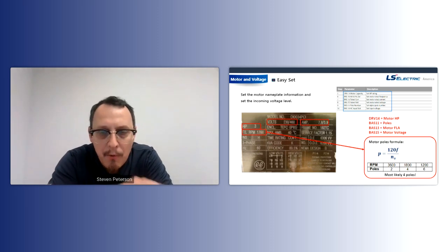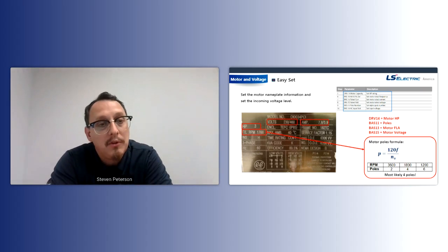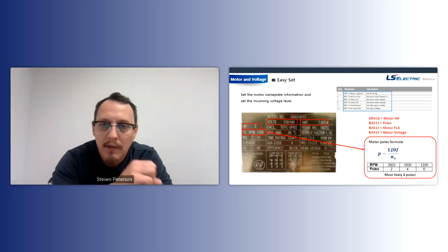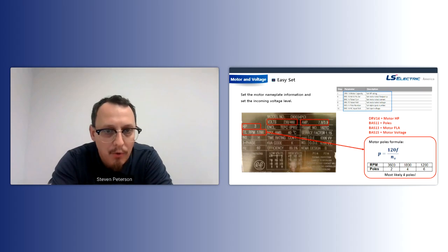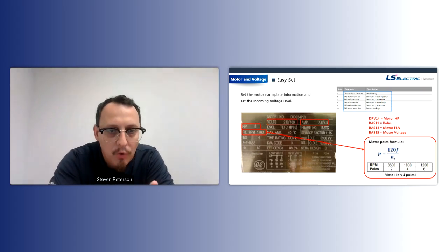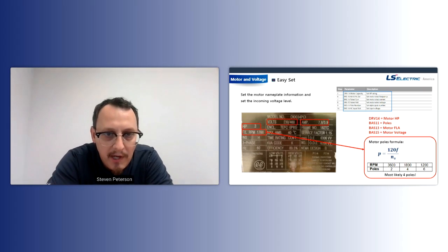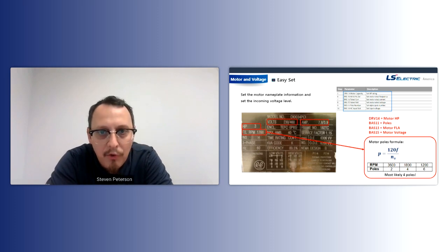The next thing is going to be your motor frequency, which most of the time is going to be 60 hertz. After that, you have rated current. And I always mention to people, this is one of the most important things because this sets your overload level for your motor. Okay, so if you have a 10 amp motor, you'd program 10 amps. So on this one, it's a dual rated motor. So it's 7.8 amps at 230 volt, and it's 3.9 amps at 460 volts.